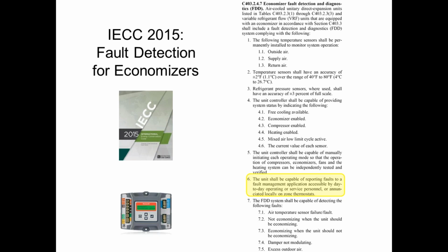So it's got to be tied down to a building automation system, and then that BAS can pop up on my screen, or it can text message me, or something like that would be acceptable. But it cannot be the screen inside the unit itself. And if you go to the state website under interpretations, they will specifically tell you that. Or if you don't want to do the BAS route, you want to have a regular simple system, you can annunciate the alarm locally on the zone thermostat. So if your thermostat can display the alarm message, then you can do it that way instead.